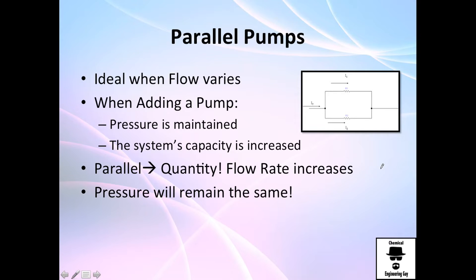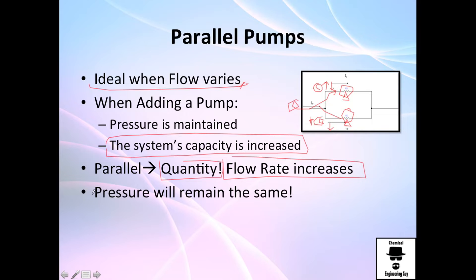So let's talk a little bit on parallel arrangement. It's ideal when the flow varies, so if you're changing, you can always increase or decrease the flow rate because you're going to split it, so the load is relatively lower in general. The pressure is maintained, and the system capacity is increased. What do we mean with system capacity? This means that the quantity or flow rate increases, and pressure will remain the same.